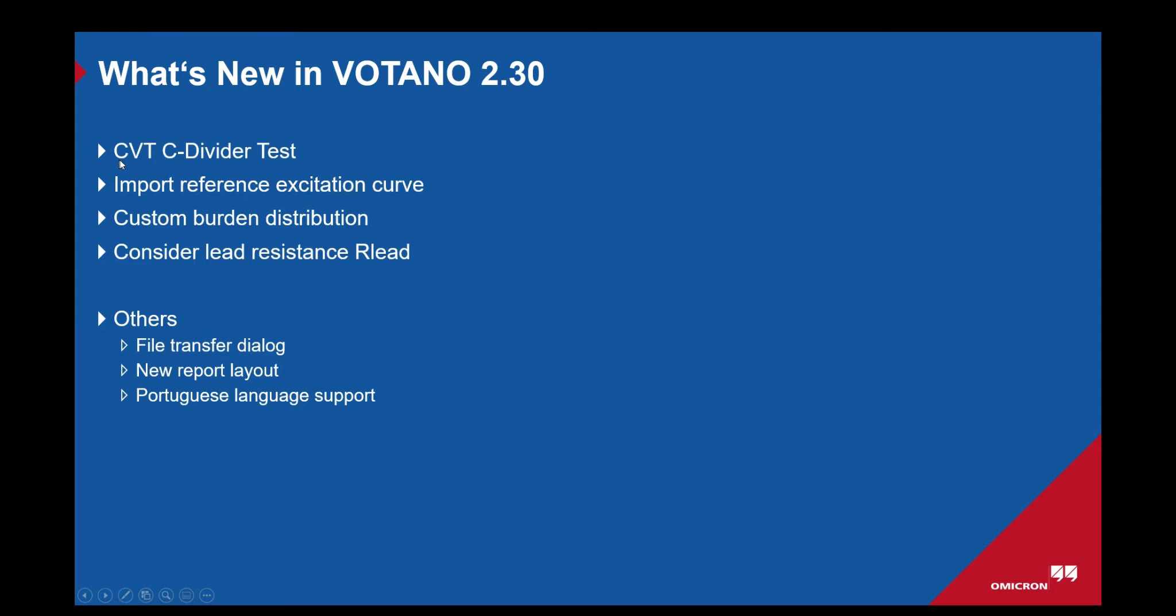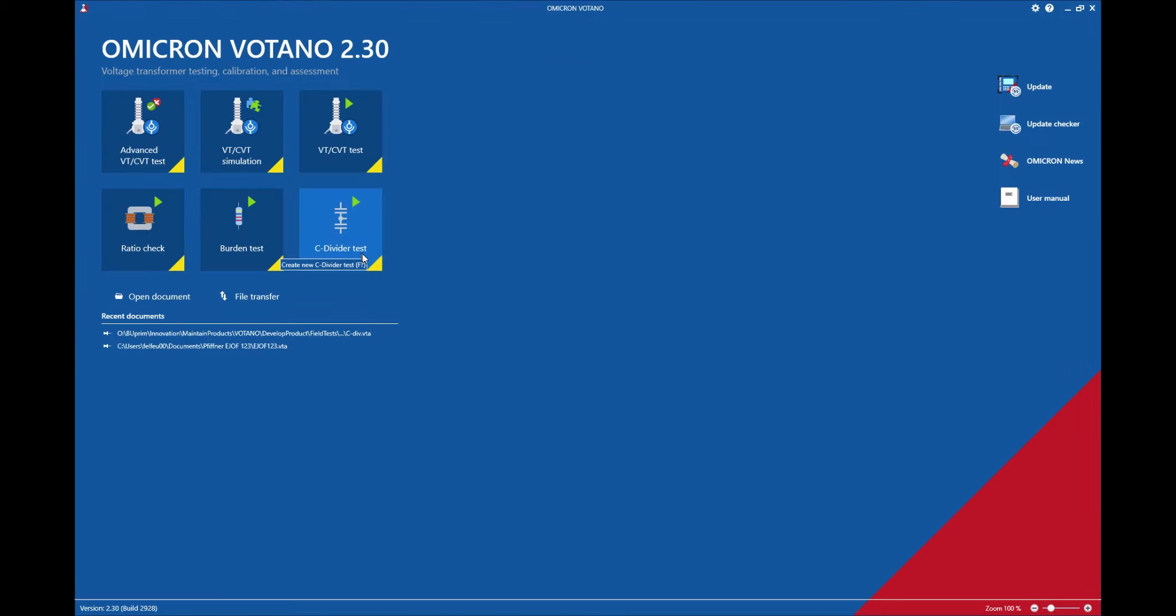First, let's have a look at the CVT C-divider test. This one is located right here on the start screen of the Votano software and it's a completely new test method that is aimed at testing the capacitive stack of CVTs.